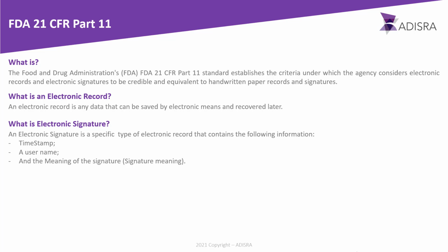For each important event, the electronic signature will be requested, and it will be necessary to enter at least 2 user identification data. These events are recorded in the system event log, known as the Audit Trail. The Audit Trail is the main traceability tool that is used to explore process problems. So if there is an operation failure, it is possible to extract information from the Audit Trail system event log to understand the sequence of events that occurred at the time of failure.